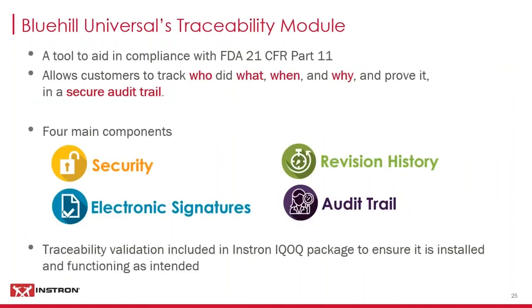Not to steal Elaine's thunder from her webinar this afternoon, but I wanted to briefly touch on traceability as it relates to IQOQ. As Jim mentioned briefly, Blue Hill Traceability is a tool to aid in compliance with Part 11. To reiterate, this is a different standard than Part 820, which governs IQOQ, but many companies must comply with both standards. There are four main components to traceability: security, revision history, electronic signatures, and the audit trail. These components allow customers to track who did what, when, and why, and prove it in a secure audit trail. Validation of the components of the Blue Hill Traceability module is incorporated into the Instron document package. As with the standard Instron OQ, objective evidence is provided where relevant to ensure robustness of the documents in the event of an audit. For more information on traceability, be sure to attend the webinar this afternoon.